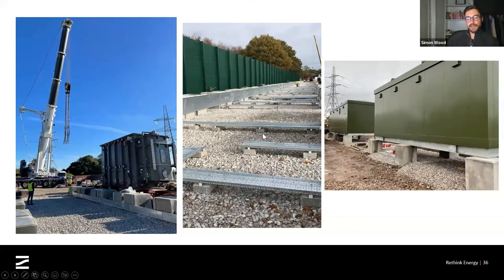So what you can't see from that first picture is a plethora of containment and cabling that's required to connect all of the different containers and equipment together. And then we have these pre-assembled control buildings, which house both the LV switchgear and the MV switchgear, all of the control systems, the protection systems that we have in place, metering, all of the ancillary equipment required to form the power system, and the power station sits within these modular buildings.